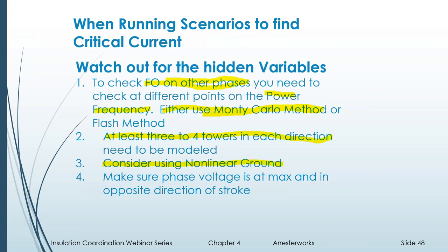I use a nonlinear ground. I think when I'm out in a tower, I use nonlinear ground because that's what happens. In a substation, I always use a linear ground, and it's always low. I'm not dealing with 10s and 20s and 30 ohms. I'm dealing with 0.5, 0.6, 1 ohm kind of grounds.